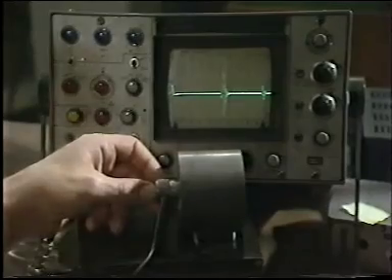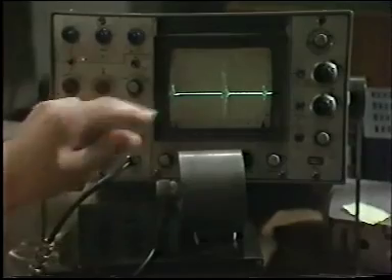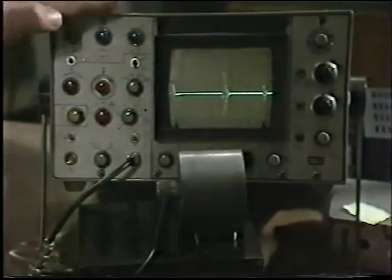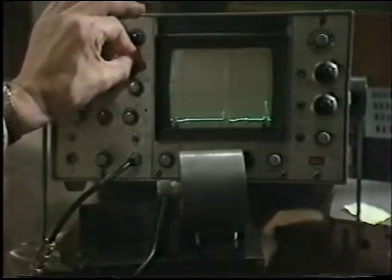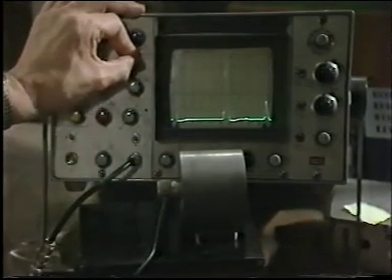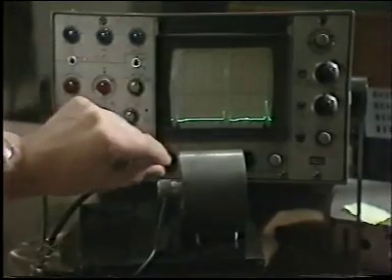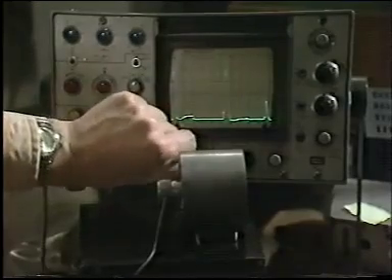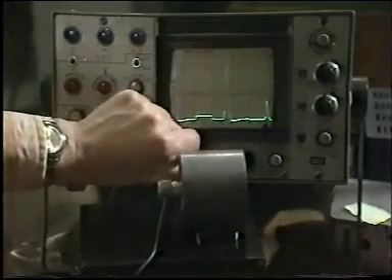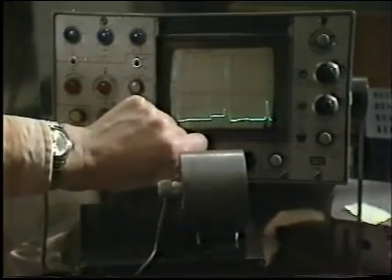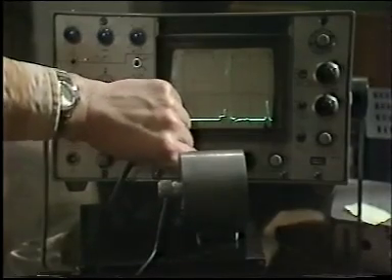Now, so far, we've seen the ultrasonic waves as they actually appear, but it's quite common on machines like this, which is in fact a flaw detector, to rectify and smooth the wave like that. And this is amplified as well, so we get a simpler display. Another facility that this sort of machine has is that we can move a range gate or time gate, which you can see I'm moving now, into the vicinity of a flaw. And when that happens on this particular one, you can hear an alarm signal goes.